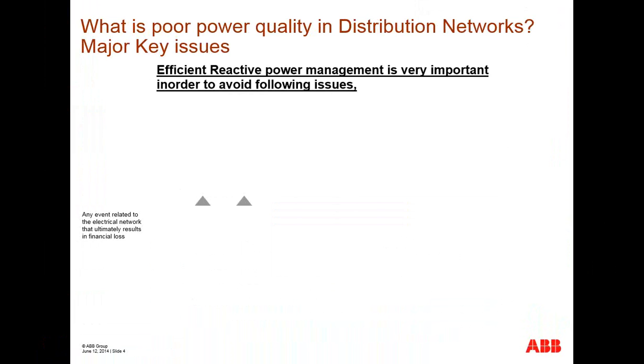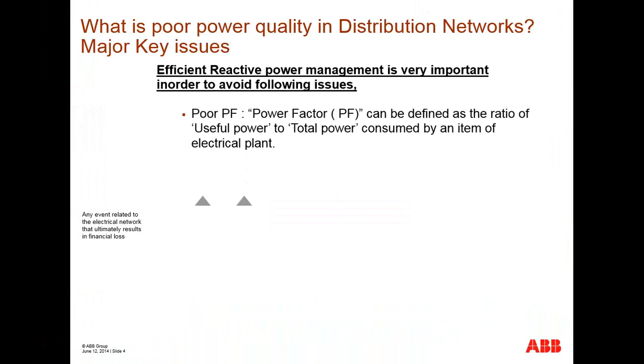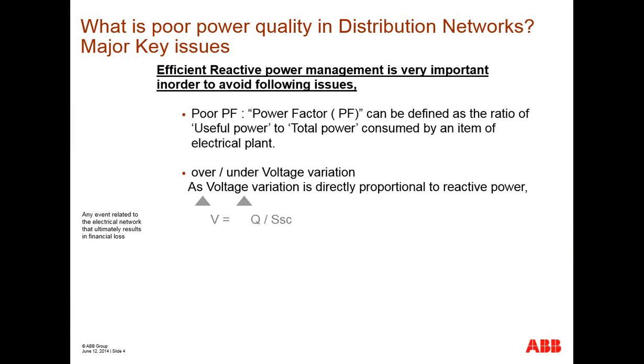So if you look at these key issues, improper management of reactive power is causing poor power factor. As you know, power factor is nothing but the ratio of useful power to total power. If reactive power is not managed properly, it also causes under voltage and over voltage variation, as the rate of change of voltage, delta V, is proportional to the reactive power variation, and it depends on the short circuit level. So the higher the short circuit level, the lower the voltage fluctuation.